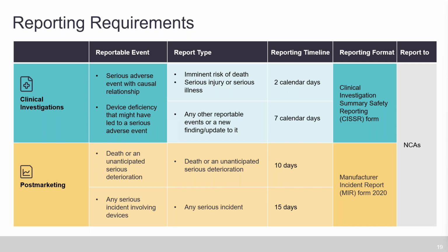So this slide is just a summary of what I have said on the reporting requirements. If you go through the MDR guideline, there are a lot of articles you have to filter through. But this is a gist of it, to understand the requirements on the clinical investigation and the post-marketing front. As I said, on the clinical investigation side, it's 2 and 7 calendar days.